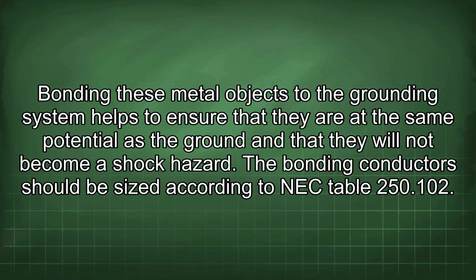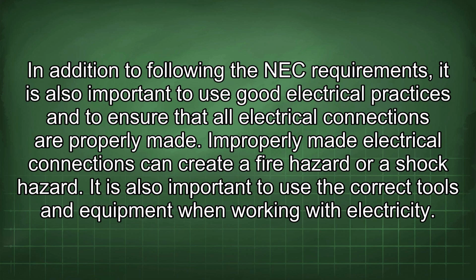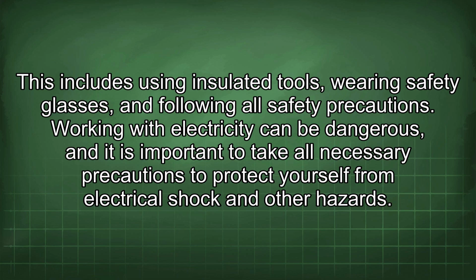The bonding conductors should be sized according to NEC Table 250.102. In addition to following the NEC requirements, it is also important to use good electrical practices and to ensure that all electrical connections are properly made. Improperly made electrical connections can create a fire hazard or shock hazard. It is also important to use the correct tools and equipment when working with electricity. This includes using insulated tools, wearing safety glasses, and following all safety precautions.